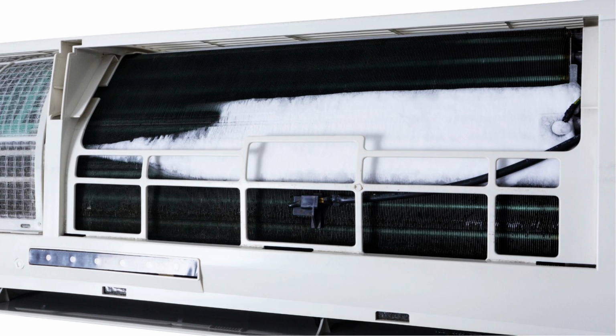This can be caused by a dirty air filter, clogged condensate line, or blocked ductwork. Malfunctioning fan. If the fan that blows air over the coils is not working properly, it can also cause them to freeze. Improper installation. If the HVAC system is not installed properly, it can lead to a number of problems, including frozen coils. 2. How can I tell if my HVAC coils are frozen?